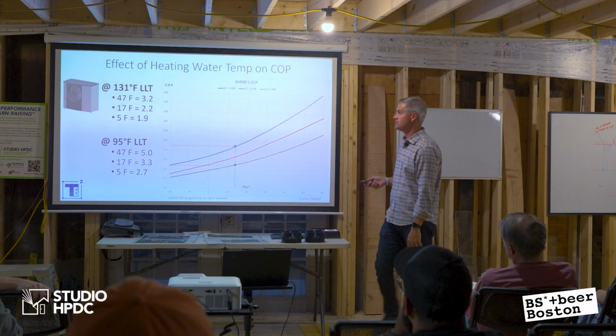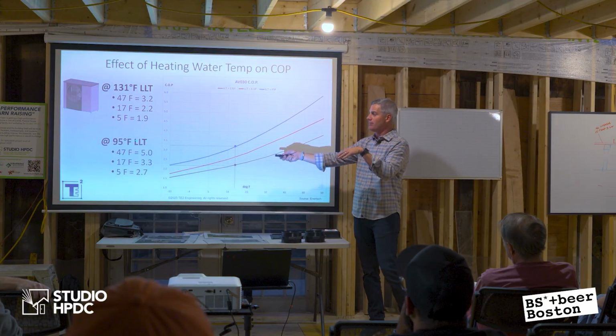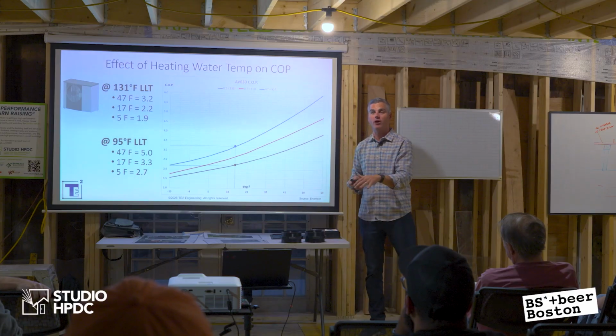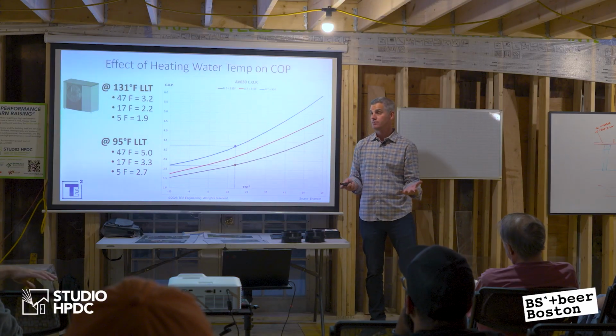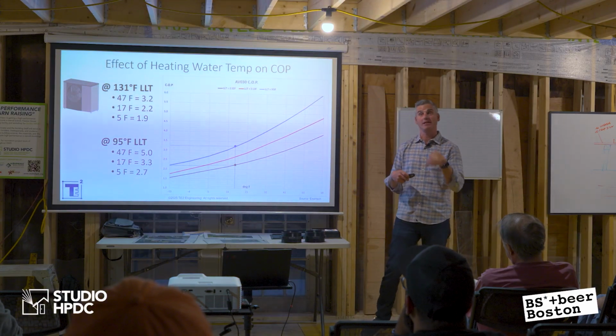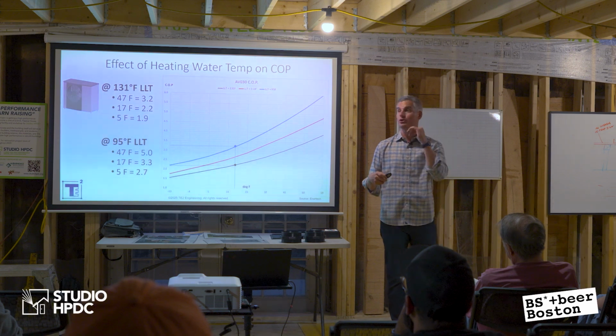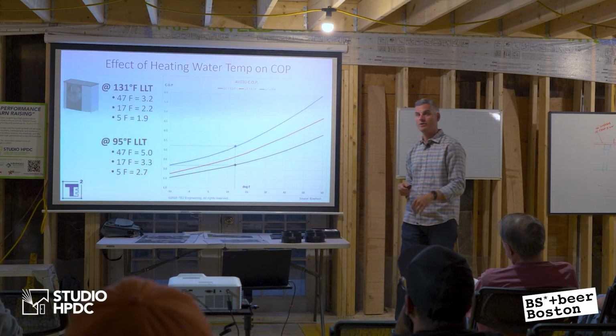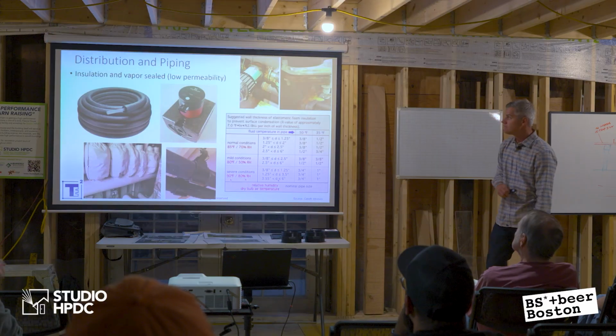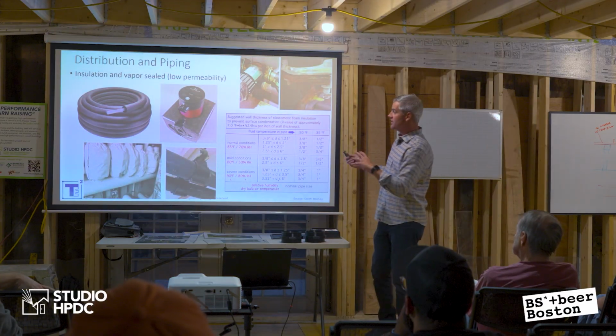Not as advantageous. So the key for us is to get the water temperatures delivered to the space as low as possible to still heat the space in heating mode. And the same thing in cooling, to get it as high as we can with chilled water temperatures so we can get the best efficiencies in cooling. I'll do a bunch of questions at the end if you want to hold them. So what are the things you have to be worried about?